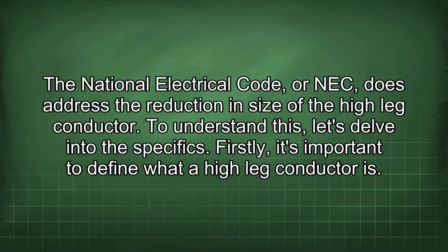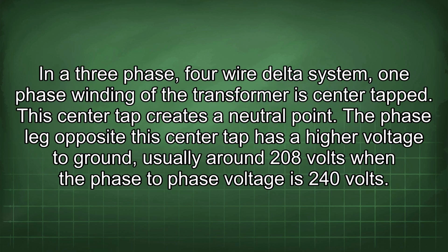The National Electrical Code, or NEC, does address the reduction in size of the high-leg conductor. To understand this, let's delve into the specifics. Firstly, it is important to define what a high-leg conductor is. In a three-phase, four-wire delta system, one phase winding of the transformer is center-tapped. This center tap creates a neutral point.